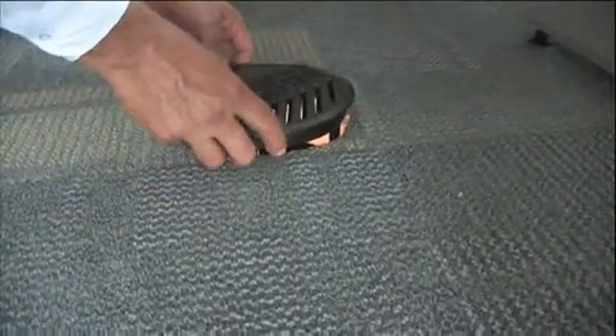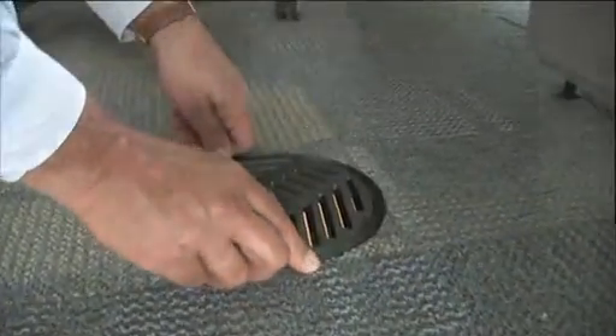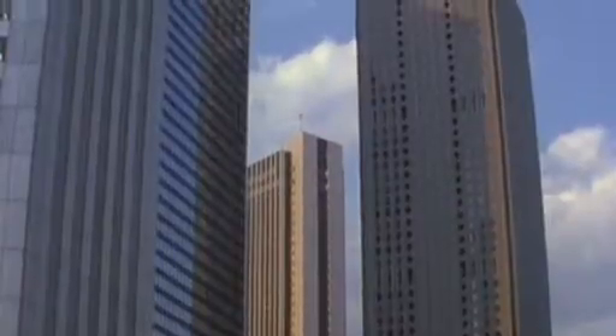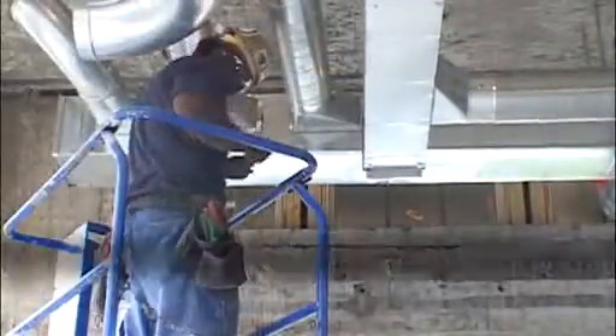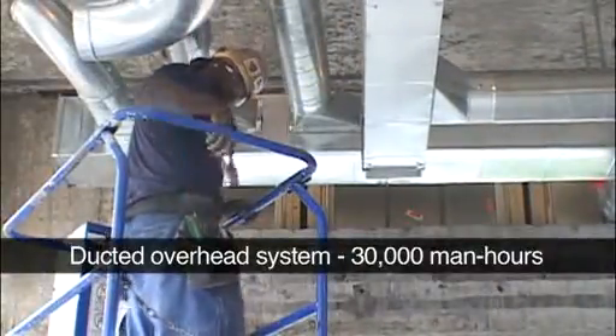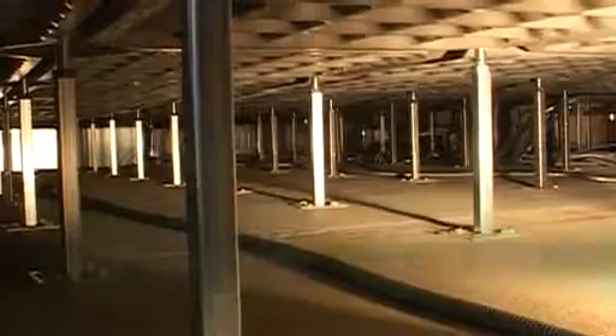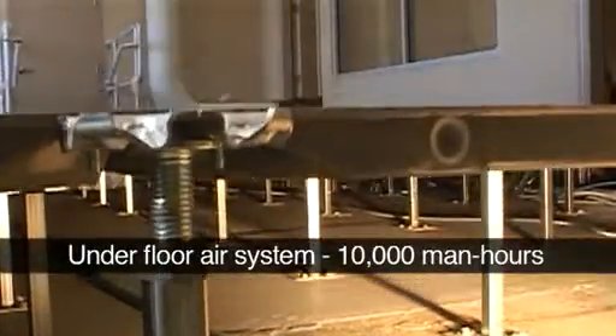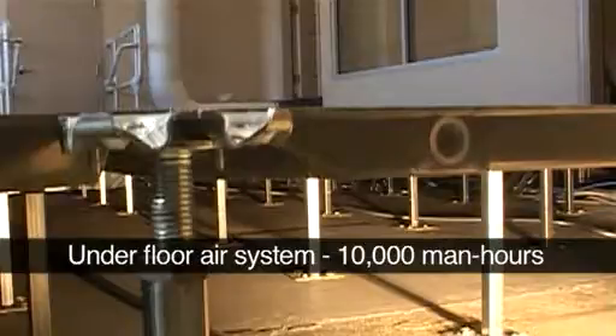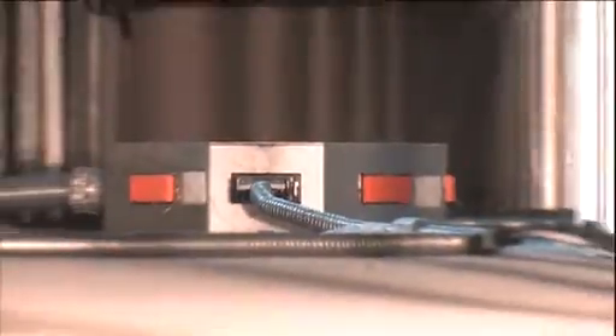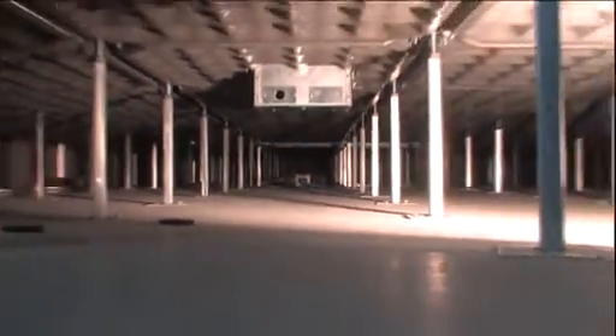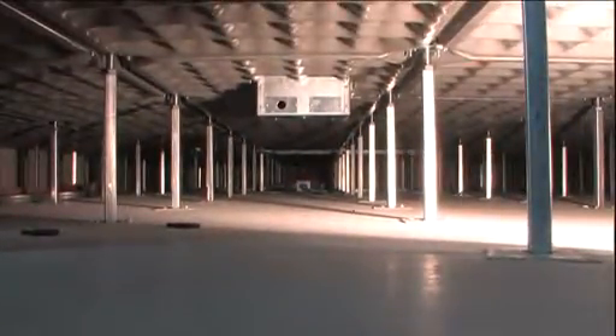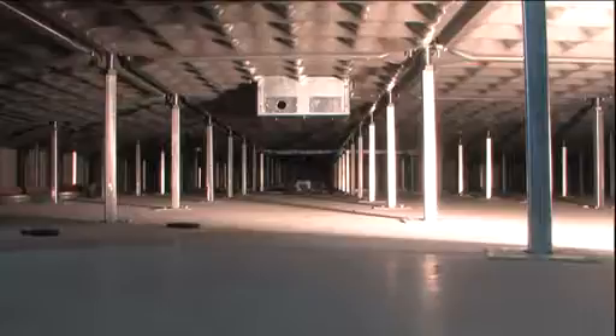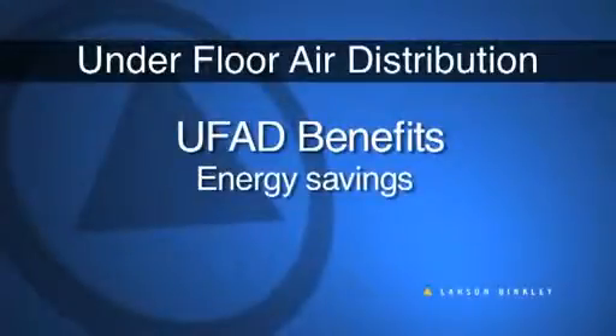On-site, underfloor air delivers efficiencies. Experience has shown that a 300,000 square foot building with a ducted overhead system can require as much as 30,000 man-hours of field labor. The same size building using underfloor air can be as little as 10,000 man-hours of field labor. That's a considerable savings. And as you can imagine, there are far fewer traffic jams and scheduling conflicts among the trades. Many developers find the ongoing energy savings the most compelling benefit of all.